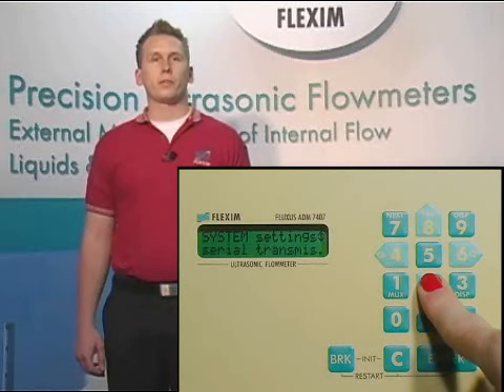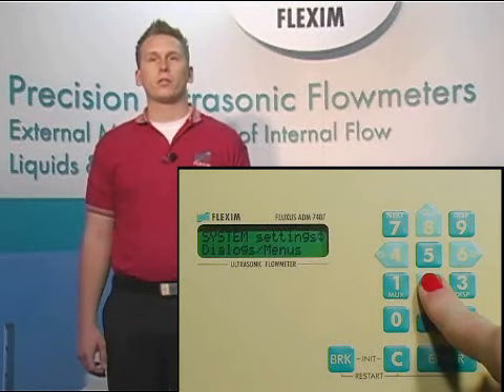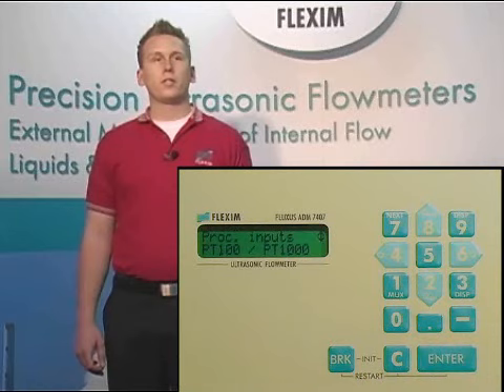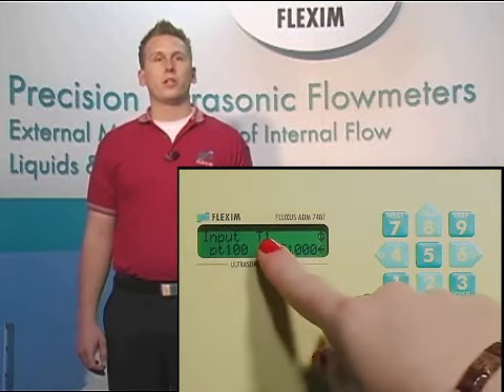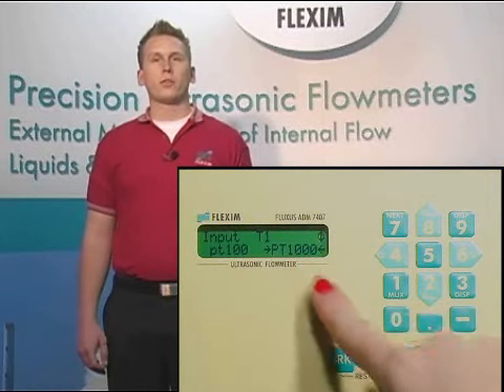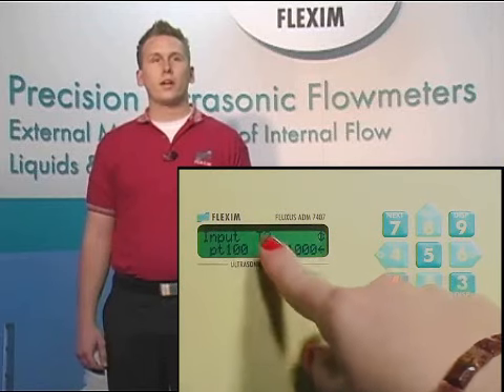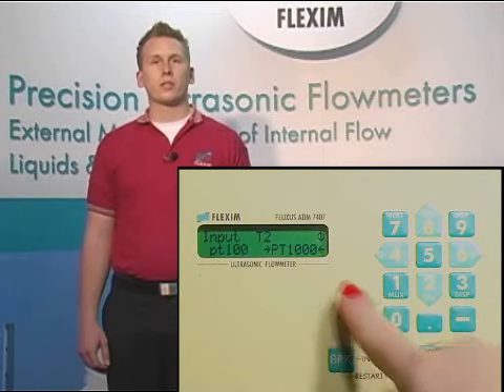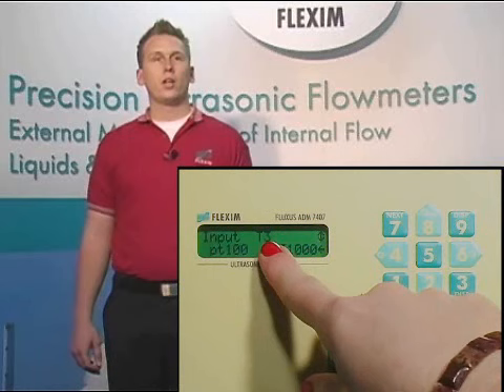In here we have 3 options, and we'll need to make sure they're all set correctly. The first is PT100, PT1000. This is where we choose which types of RTDs we'll be using. To set this, hit enter and scroll left or right to the correct type of RTD and hit enter.